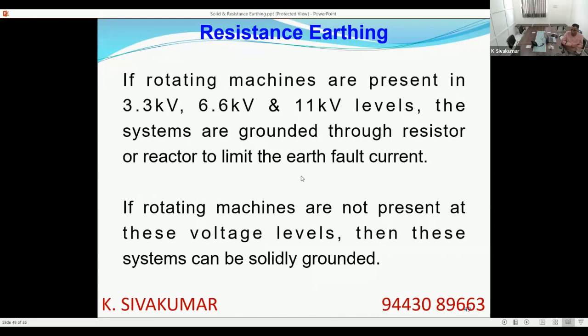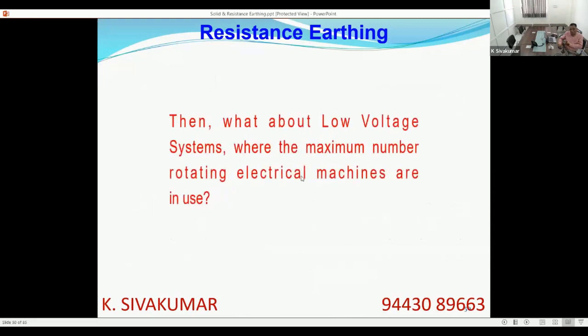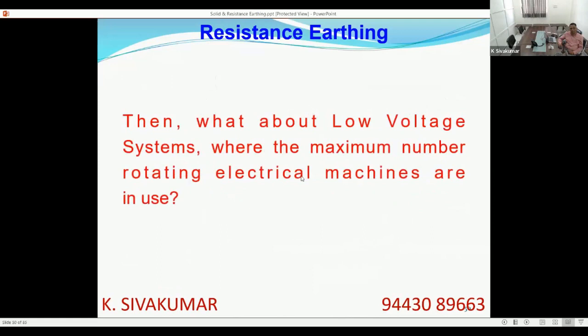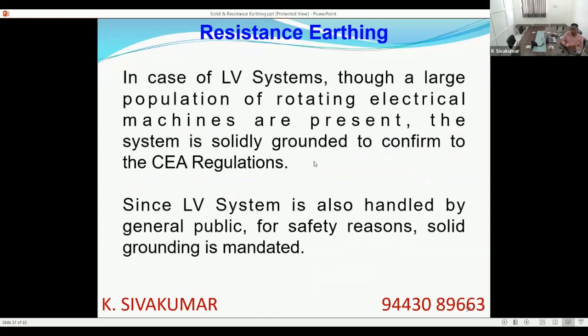But in 415 volt system, by rule, you must solidly earth. If you solidly earth the neutral, your motor is going to get damaged. Your motors are going to get damaged. So the biggest question is that low voltage system. What about low voltage system where the maximum number of rotating electrical machines are in use? But by mandate, by rules, by codes, you cannot resistance impedance earth the low voltage neutral. Low voltage neutral by IS 3043, by CEA regulation, by NEC, you must solidly earth the low voltage neutral.